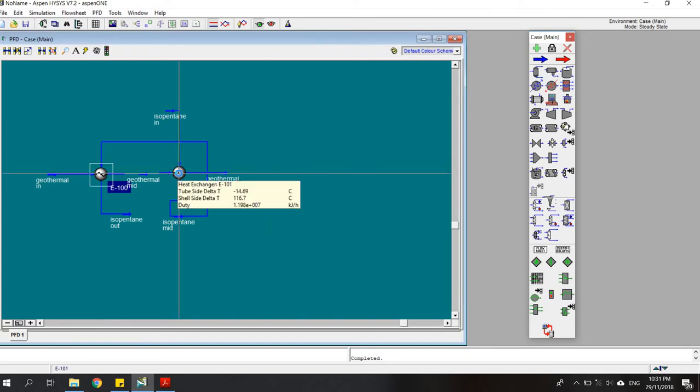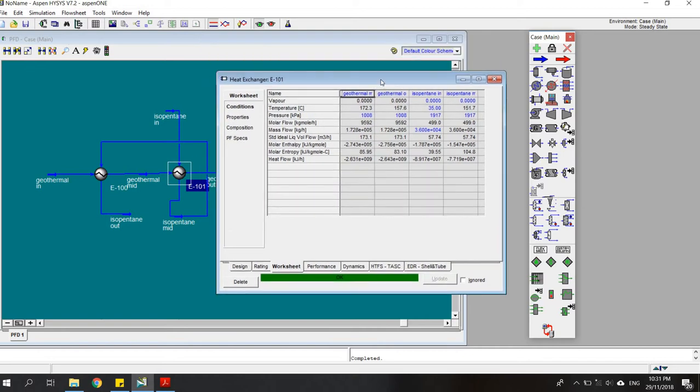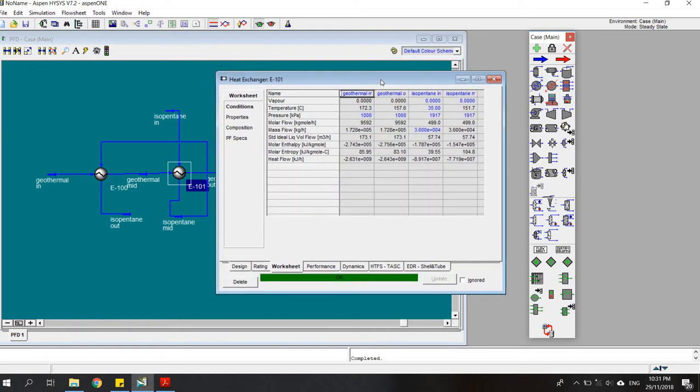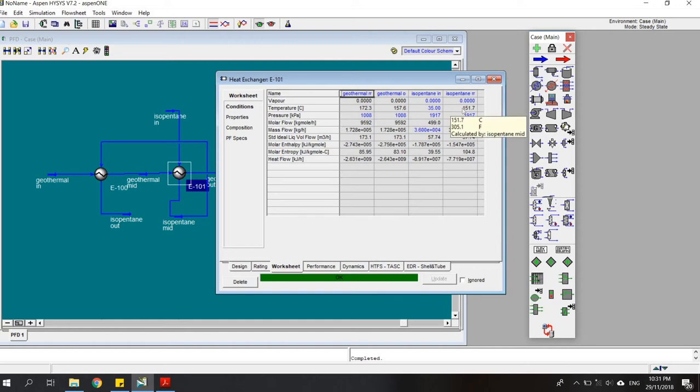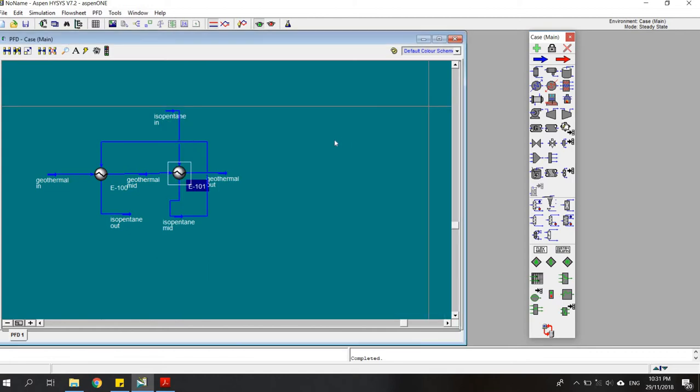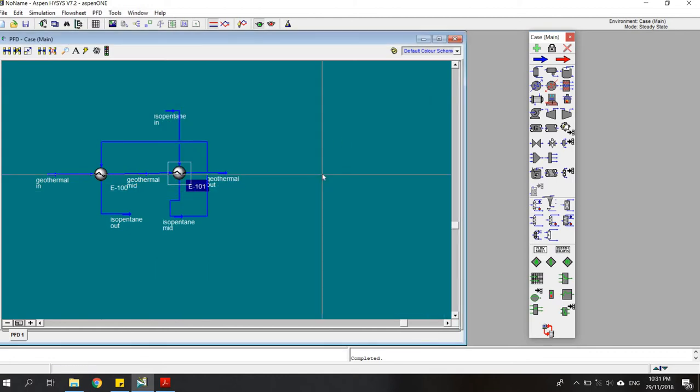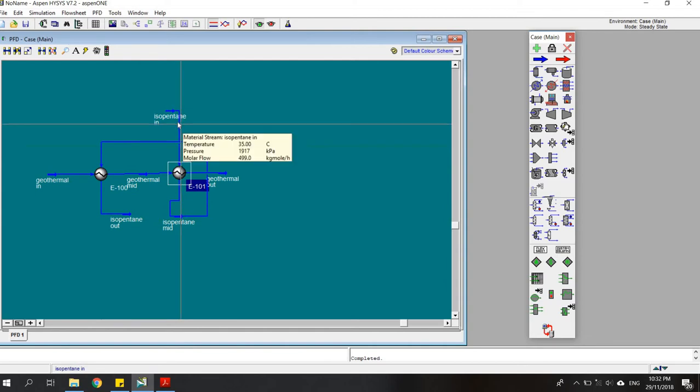In the preheater, the geothermal brine temperature reduced to 157.6 degrees and the isopentane temperature increased from 35 to 151.7 degrees. The calculation has been done for the isopentane out.